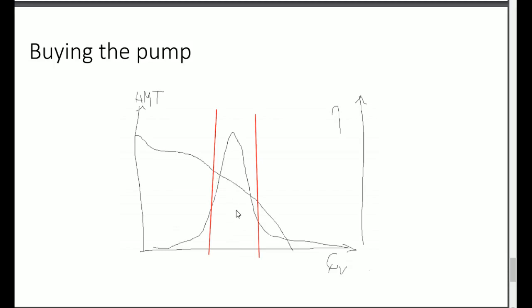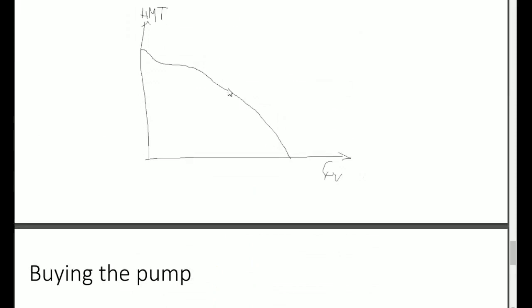And this is pretty useful because you might have an HMT QV on this diagram that is very close to what you want, but a poor efficiency away from it, meaning that it will work very fine near the line, but not very well somewhere else.